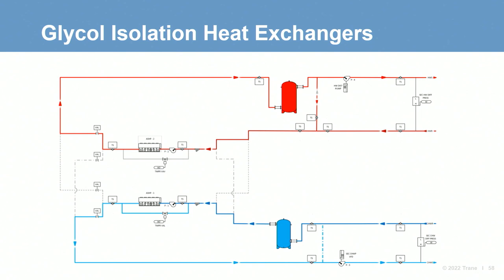First, let's talk about the fluid. The system example circulates the same fluid throughout the production circuit and heating and cooling distribution loops. Often an antifreeze solution will be desired in the outdoor production circuit so that solution will circulate throughout the distribution loops.